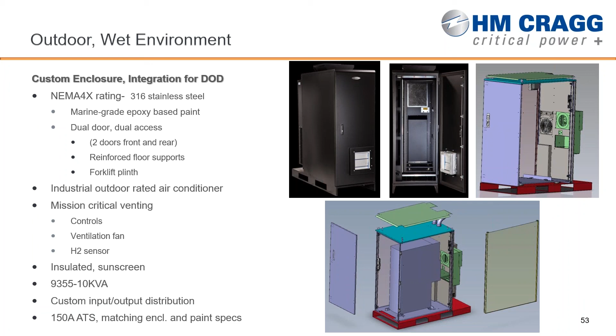So this is 2 systems that we had the requirement for utilizing the 9355 30 kVA base runtime, so internal batteries only. We have the 3-breaker bypass included, like we had talked about, in separate enclosures. So if there was a scenario where you cannot drop the load and you can throw it into maintenance bypass, the UPS or the UPS assembly itself can be completely torn out and replaced on site.